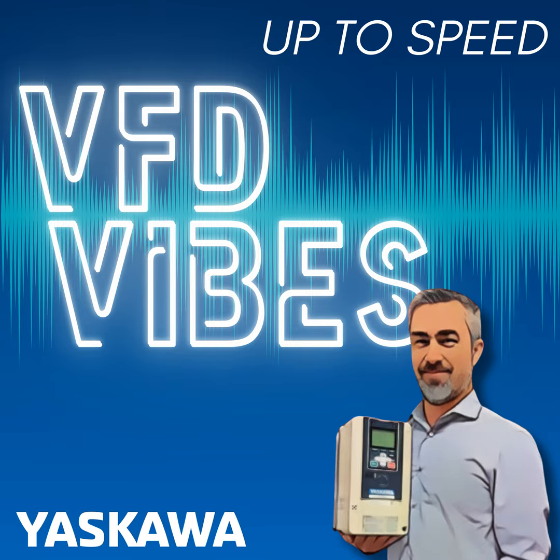Greg, during my time in tech support, you would probably be surprised how many times I got a call where we turned the power on and some smoke came out of the drive. And then we realized we put 460 volt to a 200 volt class drive. That happens, and it happens often, and it's not covered by warranty. The magic smoke. I have seen that released plenty of times in my career. And the problem with that is your customer is going to be upset with you, but your colleagues, if you're working on a maintenance crew or some kind of mechanical team with other guys, they're never going to let you live that down. Yep.